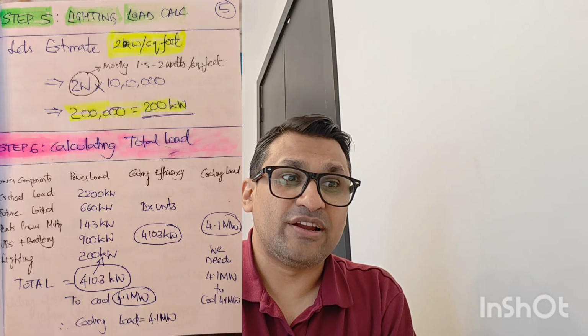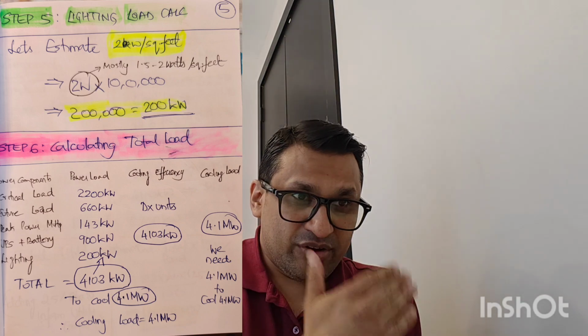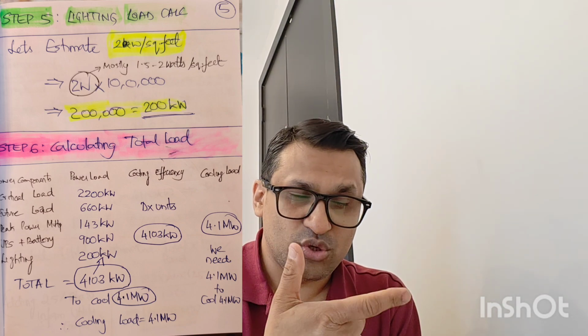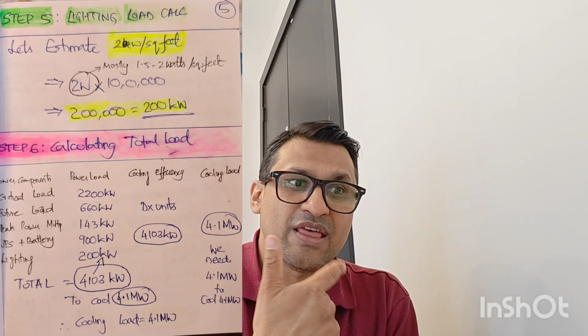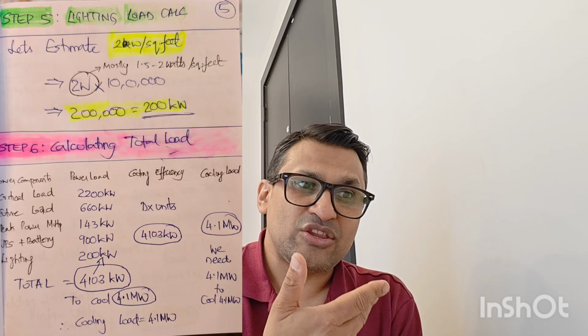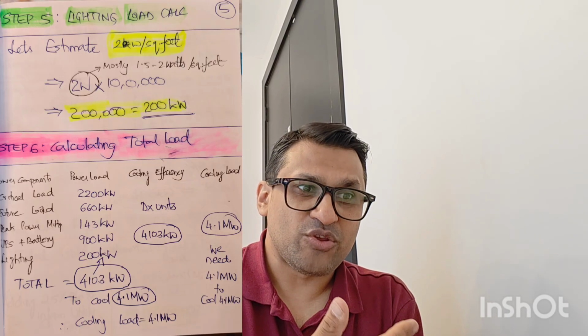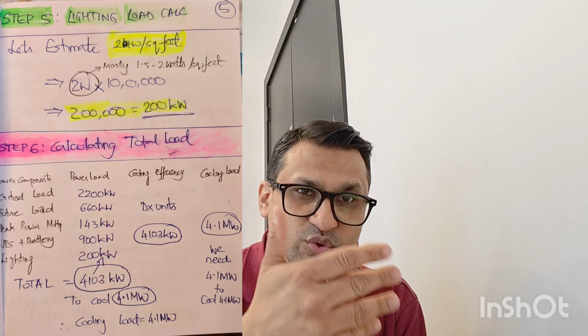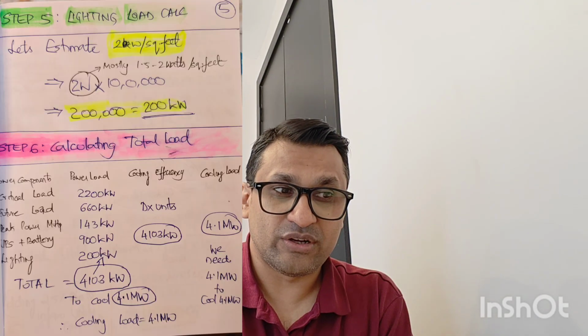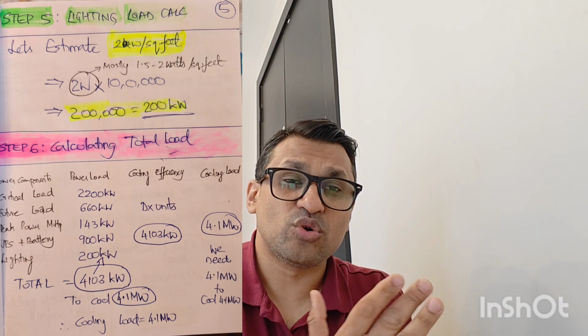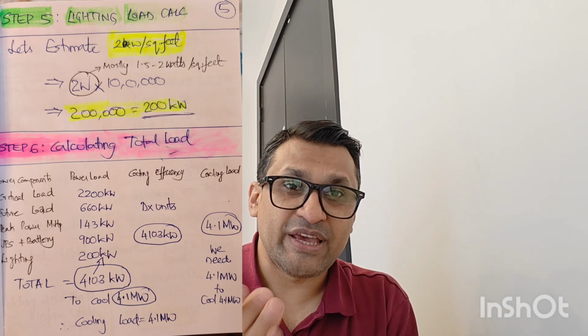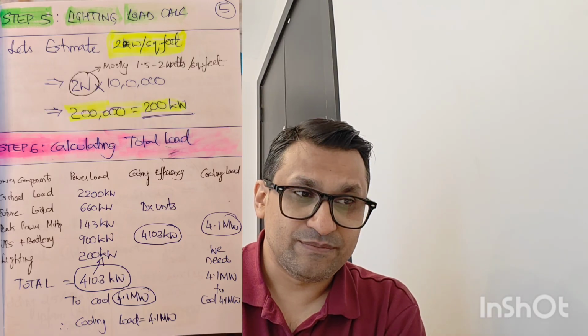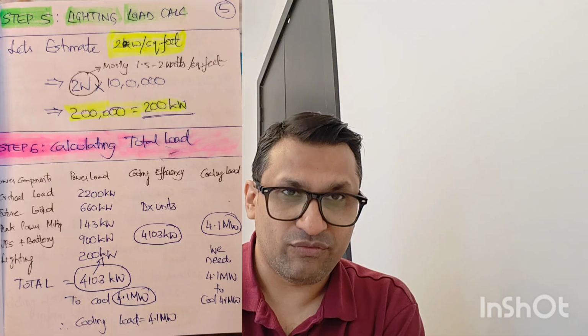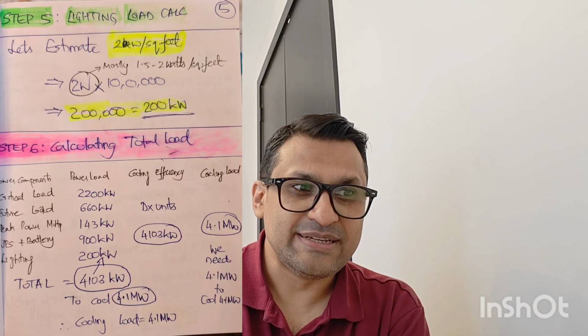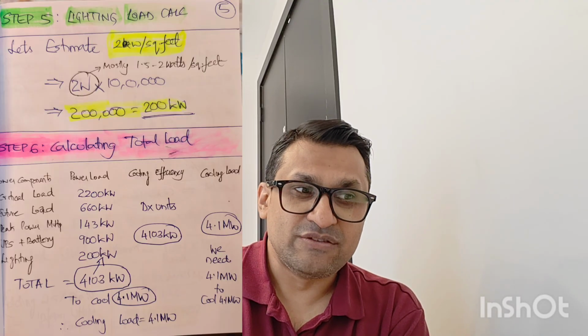So step 6, calculating the total load now. If you consider all the total load calculations, number 1 is the critical load, 2200 kilowatt. You have the future load, 660. That was 30%. And then you have the peak power multiplier, 143. And then you have UPS and battery losses, 900 kilowatt. And then you have the lighting load of 200 kilowatt. So totaling all this, 2200, 660, 143, 900, 200, you get 4103 kilowatt, 4.1 megawatt to cool. So that's the total load. That means you need to bring in cooling to that data center to cool what amount of load? 4.1 megawatt. So you need to cool the heat generated by the equipment, and that load is 4.1 megawatt.